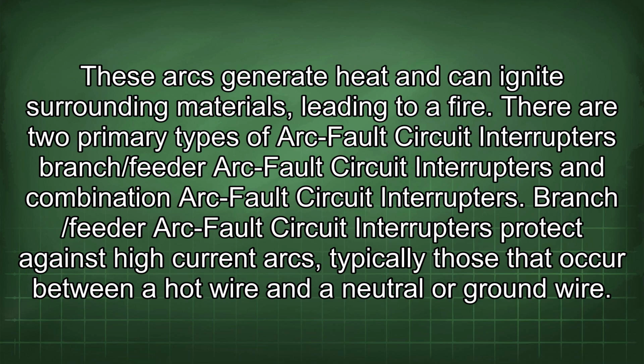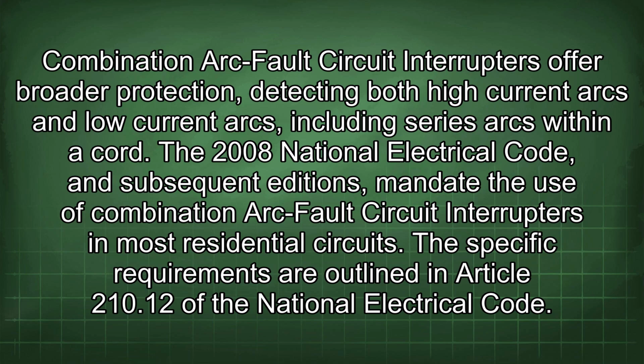There are two primary types of arc fault circuit interrupters: branch/feeder arc fault circuit interrupters and combination arc fault circuit interrupters. Branch/feeder arc fault circuit interrupters protect against high current arcs, typically those that occur between a hot wire and a neutral or ground wire. Combination arc fault circuit interrupters offer broader protection, detecting both high current arcs and low current arcs, including series arcs within a cord.